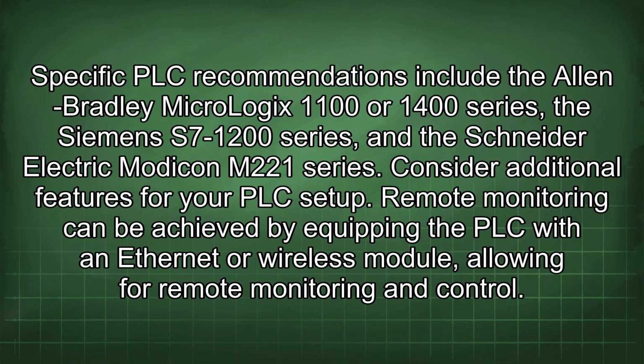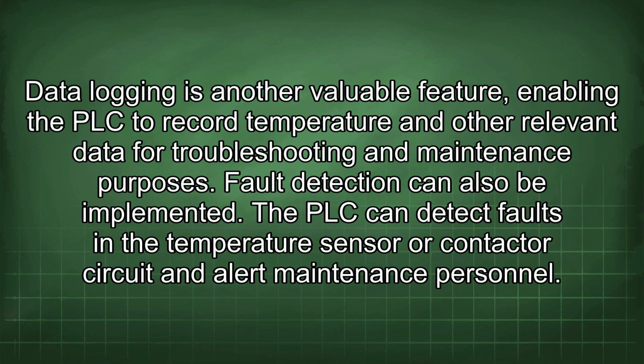Consider additional features for your PLC setup. Remote monitoring can be achieved by equipping the PLC with an Ethernet or wireless module, allowing for remote monitoring and control. Data logging is another valuable feature, enabling the PLC to record temperature and other relevant data for troubleshooting and maintenance purposes. Fault detection can also be implemented. The PLC can detect faults in the temperature sensor or contactor circuit and alert maintenance personnel.